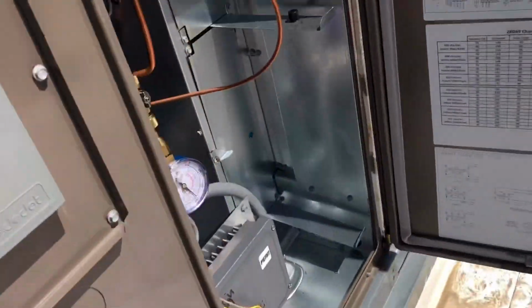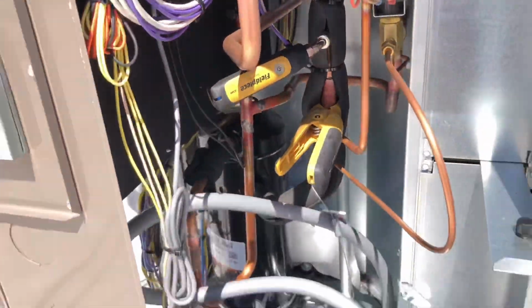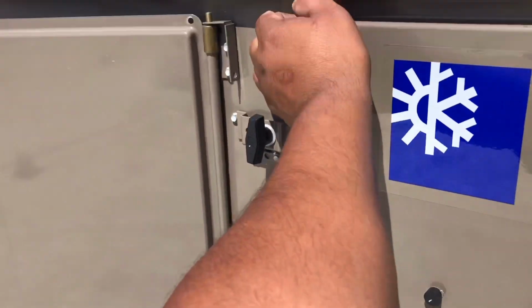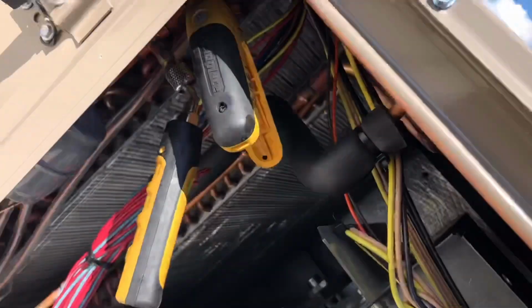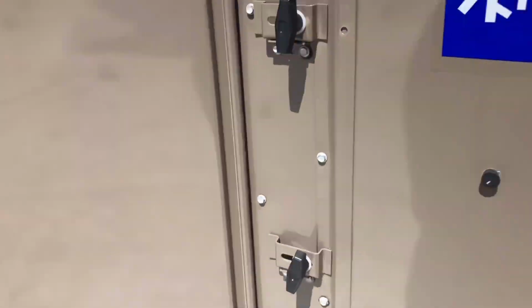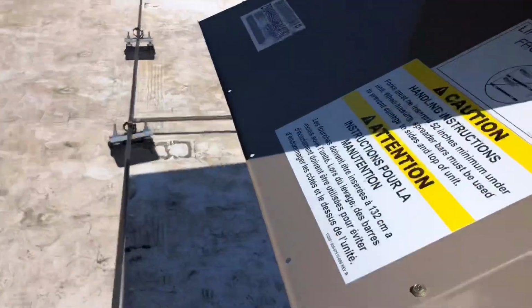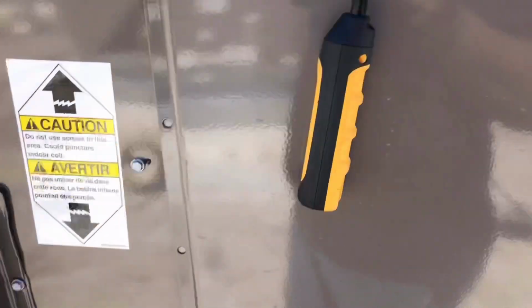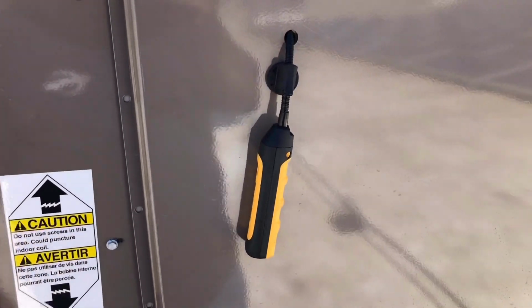Motor's running good, compressor's running good. Got the probes hooked up in there. Suction, and right in here, got our liquid line temp, liquid line pressure. And we're gonna have our return air probe right there and our supply air probe. So let's see what Measure Quick tells us.